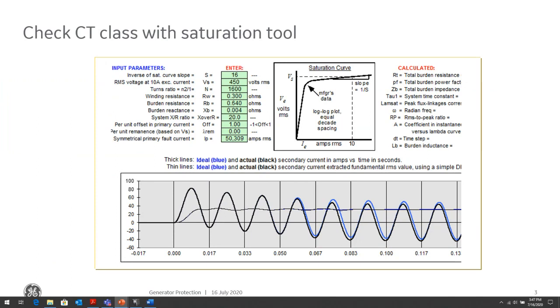Go ahead. Okay. So let's talk briefly about setting the differential, because that's a pretty important element when we're talking about differential protection. And this doesn't just cover generators, it applies to transformers, buses, and any type of equipment. One of the things we talked about is that the Achilles heel of a differential protection is saturation, because that causes differential current to flow in the circuit and could cause misoperation. There are ways we can deal with it, and we've talked about them. So, how do we select the CT to prevent saturation? One of the good tools is the IEEE working group tool. It's all available on our website. It's not a tool owned by GE. It's available on our website if you want to download it.